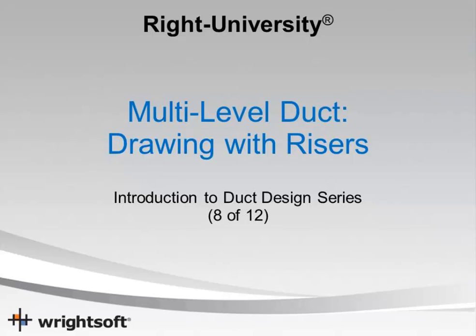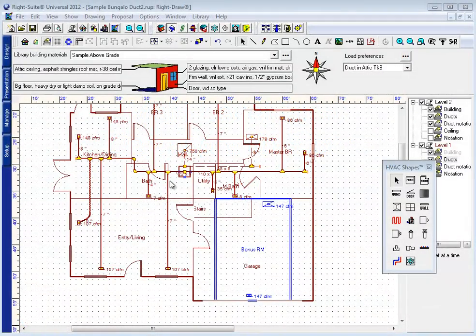In this video, we're going to look at some of the instances of having a multi-story duct system within an attic. If this duct system here is within my attic space, and this bonus room here is also built inside the attic, I should be able to connect this ductwork straight from here to these registers. The issue here is that this register out here is actually reached by going over and above and into the truss space above my bonus room.